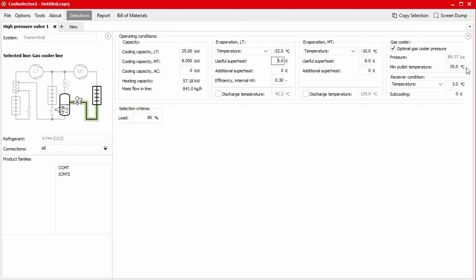For the gas cooler, you can notice that the minimum outlet temperature is required as an input. The minimum outlet temperature represents the outlet temperature in winter conditions. This is because, considering a constant receiver pressure or saturation temperature, the valve opening degree increases by decreasing the gas cooler outlet temperature. In other words, the highest opening degree of the valve is at minimum gas cooler outlet temperature. So to avoid undersizing of the valve, the minimum outlet temperature is requested by the application. In this example, we'll specify a minimum outlet temperature of 20 degrees Celsius.